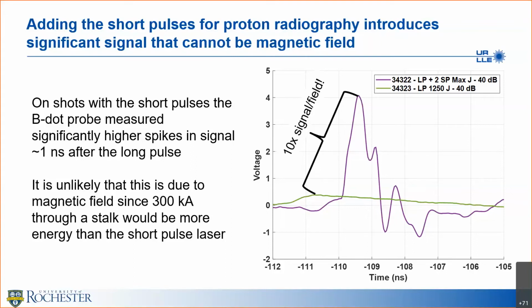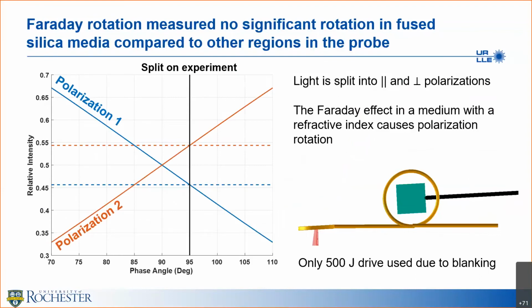So clearly the short pulse laser introduces a significant electrical field component to the BDOT probe. And this is something that we really have to be careful about when making these measurements. We did Faraday rotation, and we basically measured no significant rotation in the fused silica medium compared to other regions of the probe. The idea is that you split light into parallel and perpendicular polarizations. You split it close to 50-50, and then the Faraday effect in a medium with a refractive index causes a polarization rotation, causing more light to come through one polarization versus the other.